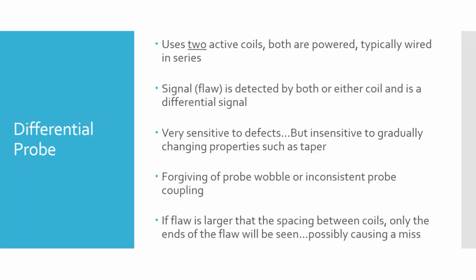The other issue you can have is if you have a flaw - like corrosion, which tends to be a larger area flaw - if the flaw is larger than the coil face itself, it can actually be hidden; you may not even see it. It's similar to that tapered property. So these are really good at finding things like cracks or very small, narrow, isolated things, but not as good at finding more widespread damage.